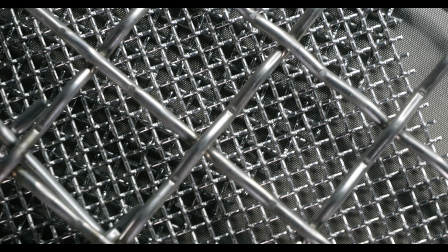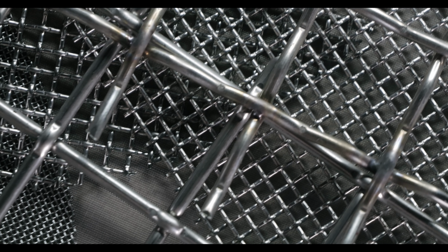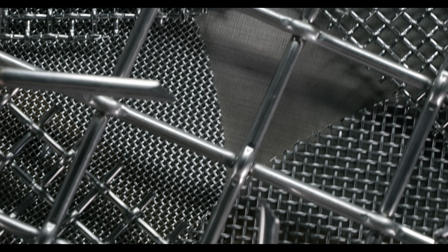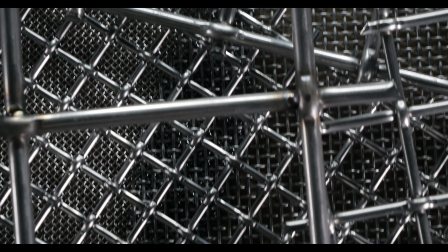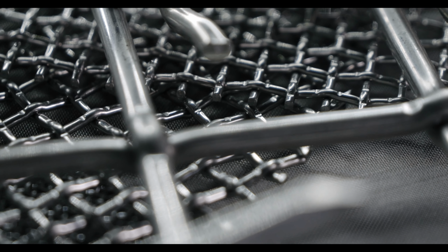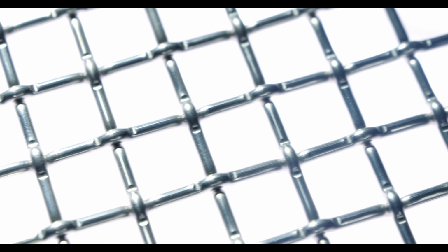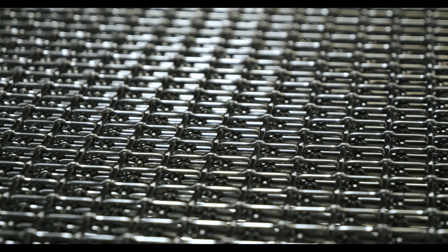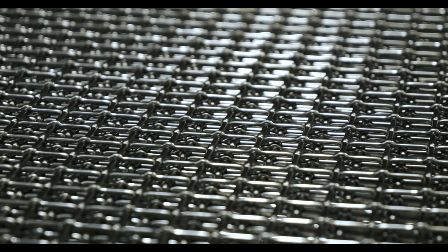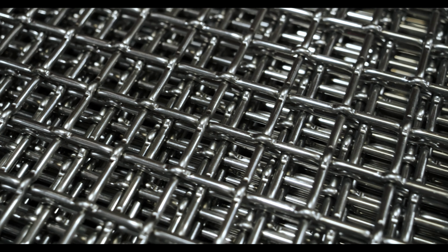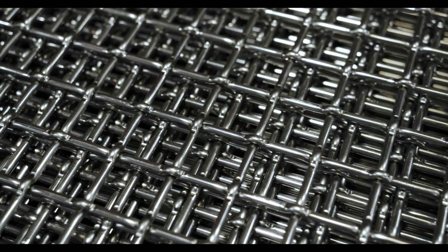Using 316 stainless steel as a minimum standard is increasingly seen as inadequate for long-term durability in desalination environments. While 316 offers moderate resistance to chlorides, it is prone to pitting and stress corrosion cracking under high salinity and temperature conditions. Upgrading to higher performance alloys such as Avesta 254 SMO, 904L, or duplex grades significantly improves corrosion resistance, mechanical strength, and life cycle reliability, reducing the total cost of ownership and helping to enhance your plant's safety.